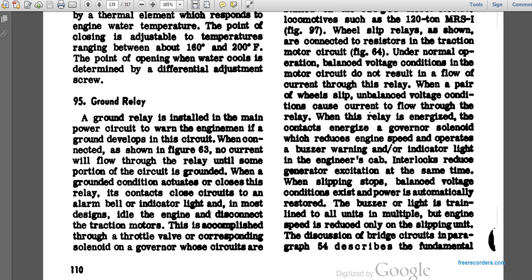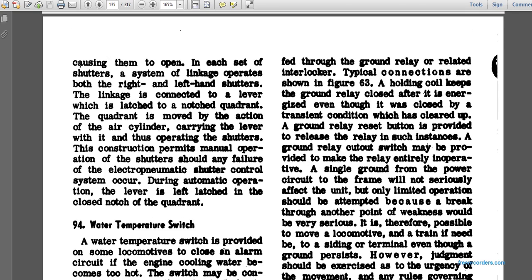Paragraph 95: ground relay. A ground relay installed in the main power circuit warns the engine man if a ground develops in the circuit, as shown in figure 63. Normally, no current flows through the relay until some portion of the circuit becomes grounded. When a ground condition actuates the relay, its contacts close the circuits to the alarm bell, indicator lights, the idle engine interlock, and disconnects the traction motor. This is accomplished through the throttle and corresponding solenoid on the governor.